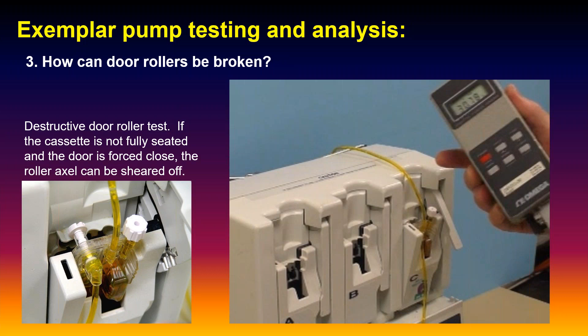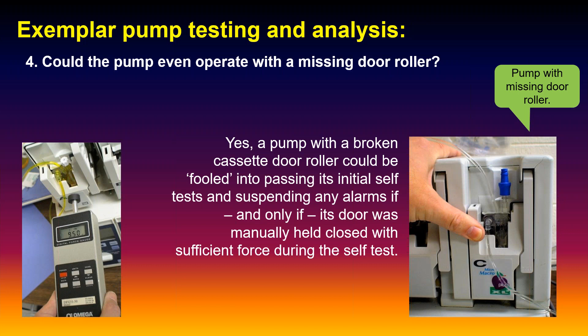I did find out, however, purely by accident, that if I held the door closed in just the right place and turned the pump on, it would go through about 10 seconds of self-check, and the pump would run with a broken door roller—if and only if I kept it closed during that period. Looking further, I found I had to apply somewhere around 3 to 7 pounds of force to make it run. Too little force and I'd get a cassette alarm; too much force and I'd get another alarm. But there was a small window where, if it was just right, you could make the pump run with a broken door.